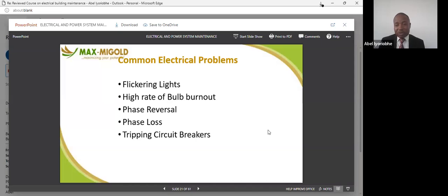This is as a result of an open circuit. Maybe there's a broken cable somewhere, so the phases are not complete. Your phase failure protection does not allow the remaining two to come in, because it will damage your equipment. Then there's tripping of the circuit breaker - a number of reasons are responsible for that. As I told you, you have to ensure the problem that caused the trip is resolved before switching the circuit back on, so that you may not be electrocuted or damage more equipment.